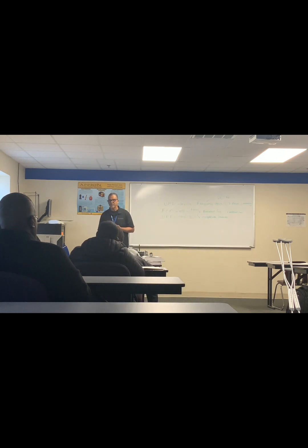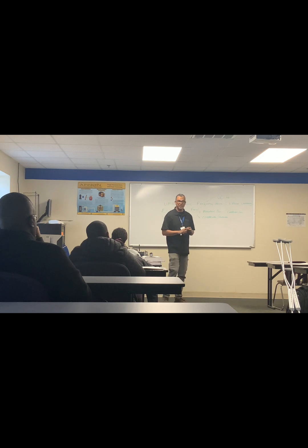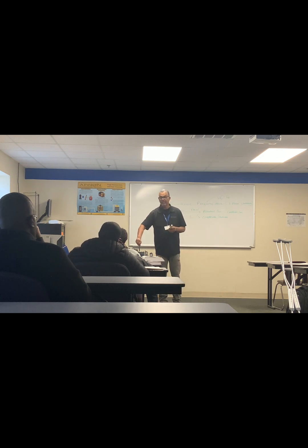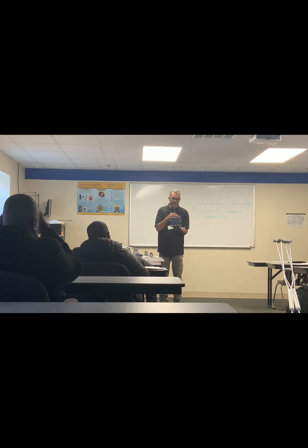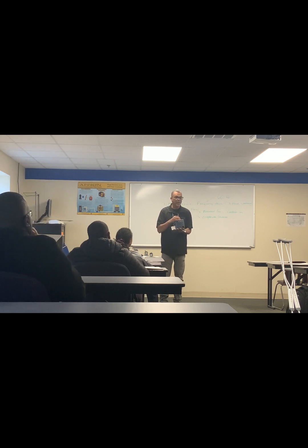It's not just the voltage, it's not just the amperage, it's also shaft diameter. How big is the shaft? Because the shaft is gonna fit into a blade or fit into a housing of an air handler, and the hole in the housing must fit this. Also, motors have a diameter that fits in a spider bracket or a bracket made for that motor that wraps around. If it's a band bracket, some of them mount upside down and have 4 bolts coming out the back that actually mount to the top of the condenser.